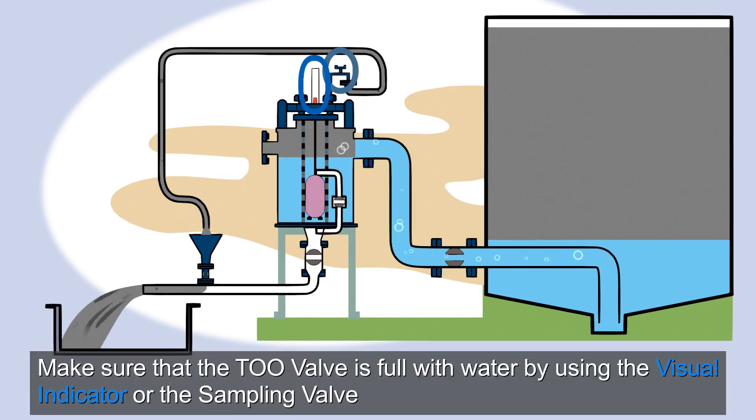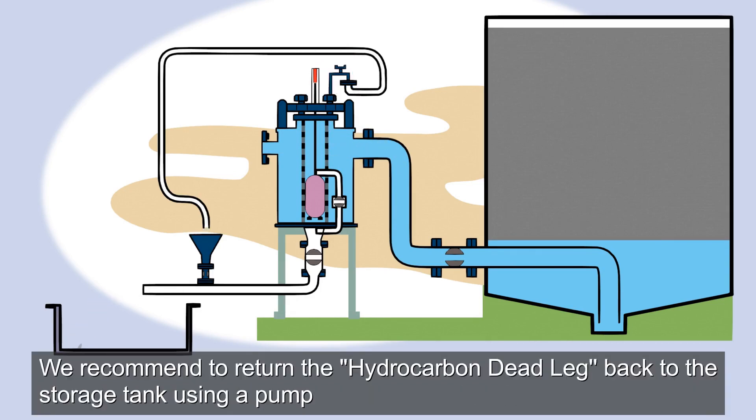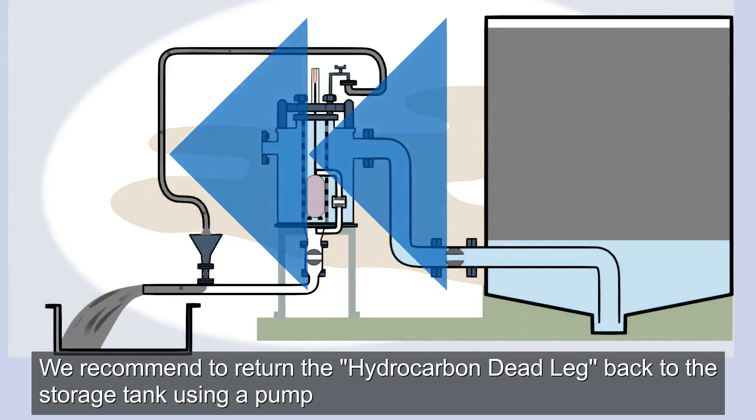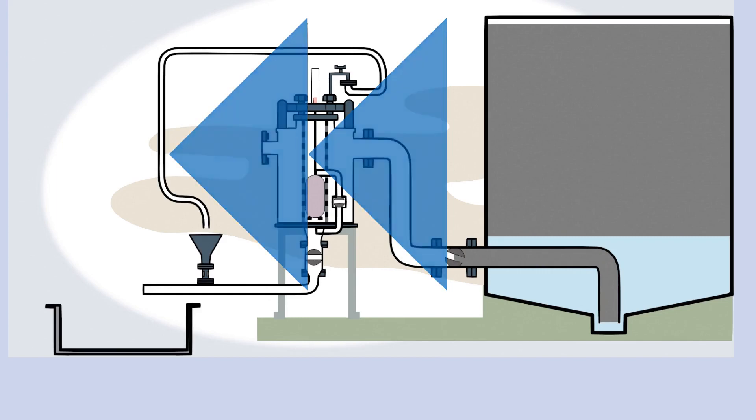Make sure that the TOO valve is full with water by using the visual indicator or the sampling valve. We recommend returning the hydrocarbon dead leg back to the storage tank using a pump. This will prevent costly wastage from the hydrocarbon dead leg and will also prevent hydrocarbon products from entering the terminal's wastewater piping system.